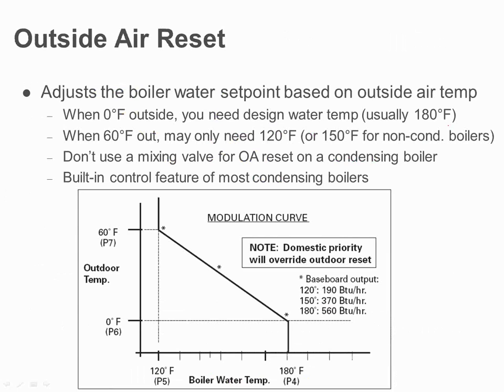Okay. Outdoor air reset is also very critical. Every condensing boiler we have out there nowadays does come with outdoor reset built in. I remember what we were talking about a little earlier about that 1% time. 1% of the year you're actually at your max output or your max Btu load. So that means the other 99% of the time you don't need 180-degree water. This is what outdoor air reset does. It basically says, okay, at a certain point along this chart, depending on where you want to go, if you look at a little star maybe in the middle, let's say that's 140-degree water temperature. So maybe at 45 degrees outside, I only need 140 to keep my building warm. So what's that doing for me? That's basically making the system run more efficiently at a lower temperature, so I'm putting less gas into the whole system, and I'm not bouncing off of 180 all the time like I do with the standard condensing boiler.